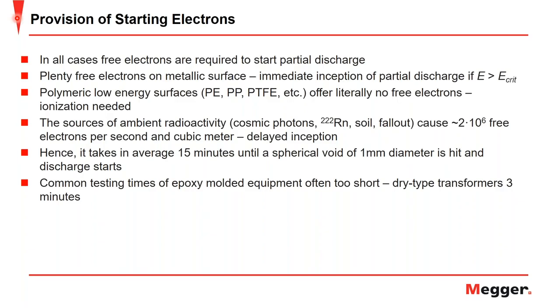And this is an issue when we talk about common test times of epoxy molded equipment, which is often too short. So it's recommended that longer test periods, at least 15 minutes or greater on epoxy molded equipment, take place to overcome the problems that would be overlooked or missed due to these internal defects having not quite taken place yet. So for one instance, a dry type transformer testing period is 3 minutes, which is only 1/5 of that statistical 15 minutes that it would take for the spherical void of 1 millimeter to start discharge.